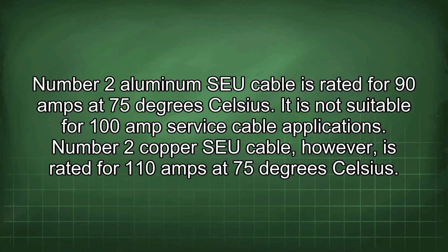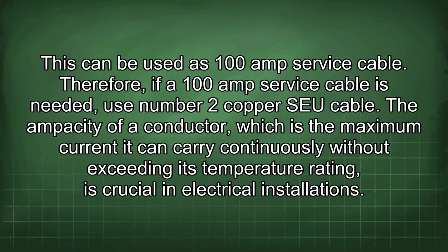Number 2 aluminum SEU cable is rated for 90 amps at 75 degrees Celsius. It is not suitable for 100 amp service cable applications. Number 2 copper SEU cable, however, is rated for 110 amps at 75 degrees Celsius. This can be used as 100 amp service cable. Therefore, if a 100 amp service cable is needed, use number 2 copper SEU cable.